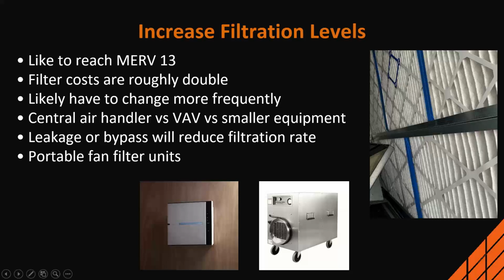We do have to be very careful about leakage or bypass. So this happens to be one of our units over here on the right-hand side. What the blue item in there is actually painter's tape. So as you put the filter in, you tape one filter to the next filter. That eliminates any bypass or leakage between the filters. And on this one, what you don't see is we've taped the accessible end, we've taped the filter to the rack. There was actually a gap there, so we taped that, so we blocked that gap. A 1/2 inch gap in a MERV 13 system will reduce it down to a MERV 8 rating. So it's very important that you get these gaps all sealed off as best as possible.